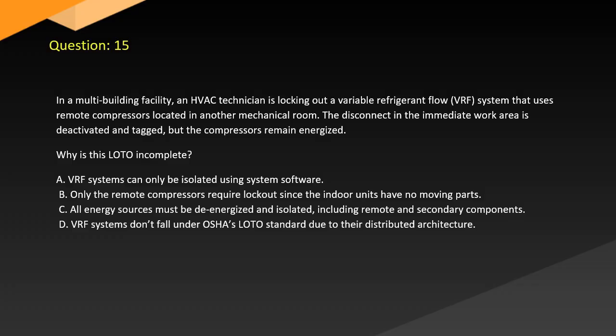Question 15. In a multi-building facility, an HVAC technician is locking out a variable refrigerant flow (VRF) system that uses remote compressors located in another mechanical room. The disconnect in the immediate work area is deactivated and tagged, but the compressors remain energized. Why is this LOTO incomplete? A. VRF systems can only be isolated using system software. B. Only the remote compressors require lockout since the indoor units have no moving parts. C. All energy sources must be de-energized and isolated, including remote and secondary components. D. VRF systems don't fall under OSHA's LOTO standard due to their distributed architecture.